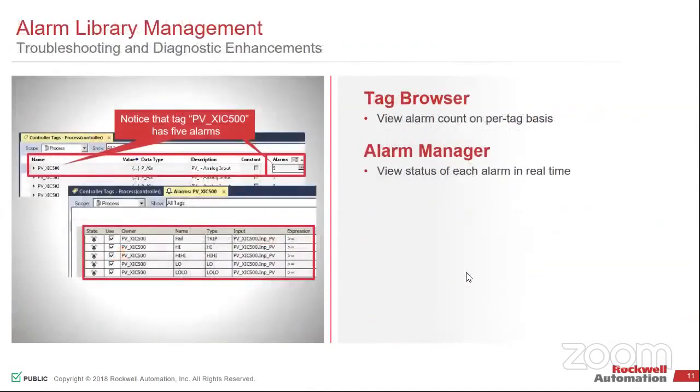One of the things that you'll see inside of Studio 5000 is a little alarm manager set. I can import and export via Excel. So the same way that I can do the HMI side of it, I can export all of the alarms that I have triggered. It gives me all of the settings on it. So it's not only just the alarm, but what triggers the alarm, what I am doing with the alarm, what the messaging is, if there are any associated tags, and if I want to do a snapshot. All of that is built into the controller. So it's the same kind of format that I would see from alarms and events on the HMI side. So I can import and export.